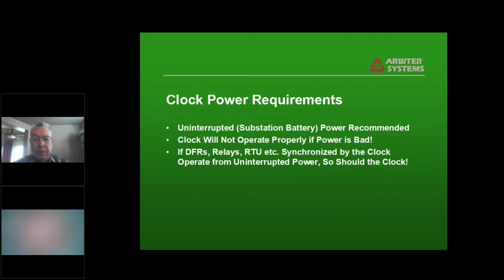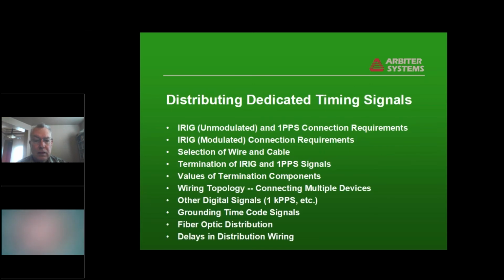Another thing to keep in mind is if you're using a clock to feed signals to DFRs, relays, RTUs, whatever is being synchronized by the clock, and they're operating from an uninterrupted power source, the clock should too, because the clock isn't going to work if it doesn't have power. So we recommend hooking everything up to a substation battery if it's possible. We're going to talk about issues with distributing dedicated timing signals, and then we're going to talk about network time after that.